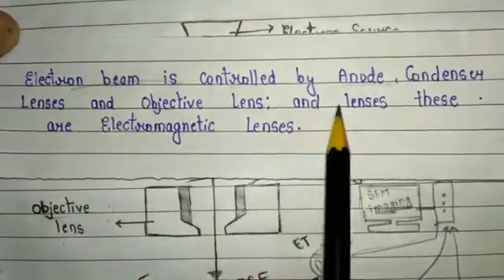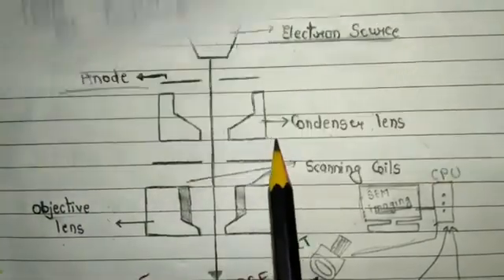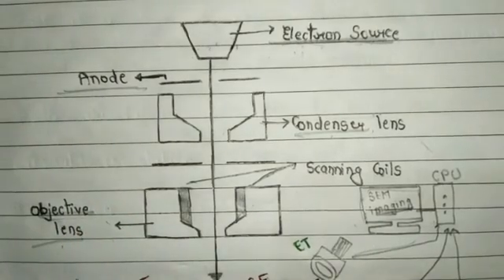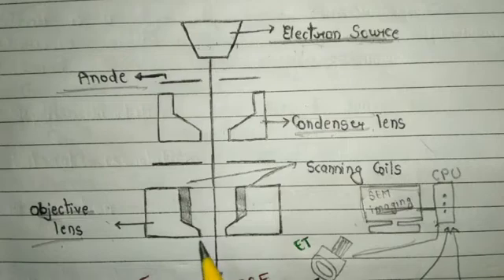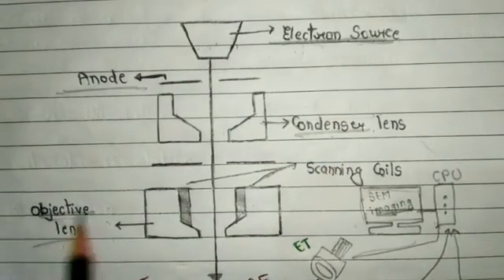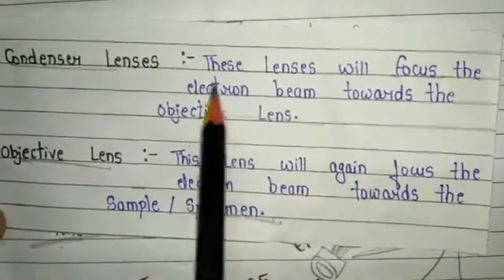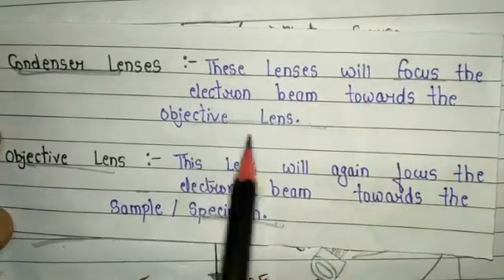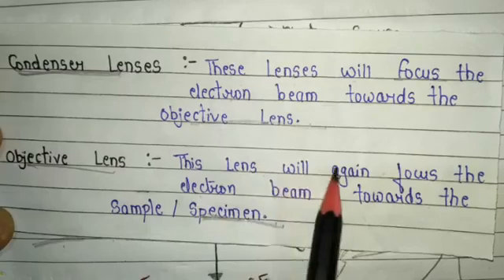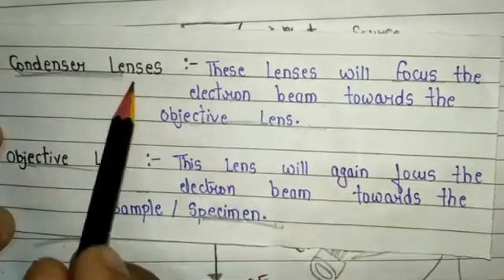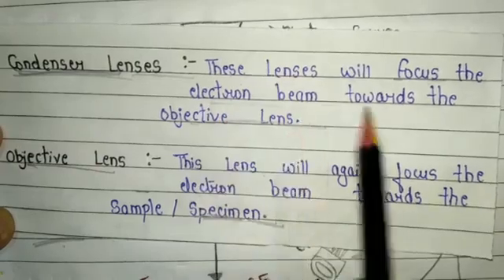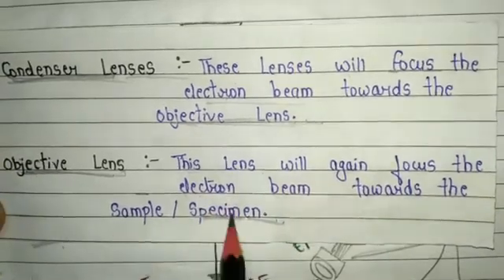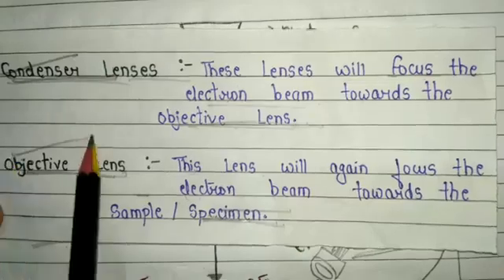Two types of lenses are used: condenser lens and objective lens. Both are electromagnetic lenses. The condenser lens focuses the electron beam toward the objective lens. So when the electron gun produces the electron beam and the anode accelerates it, the condenser lens focuses it toward the objective lens. The objective lens then again focuses the electron beam toward the sample or specimen.